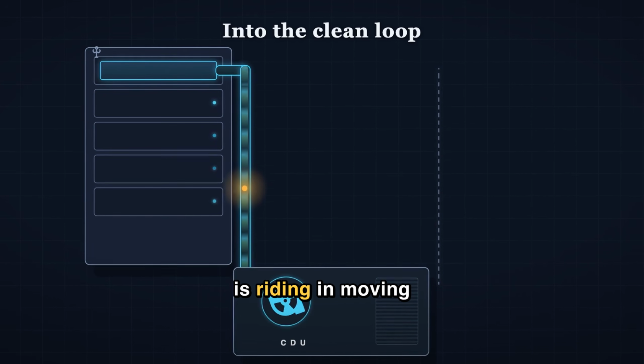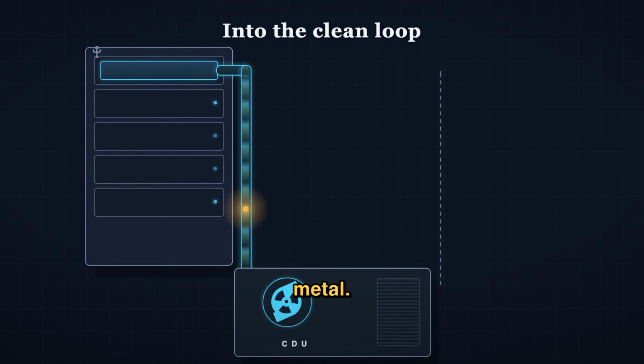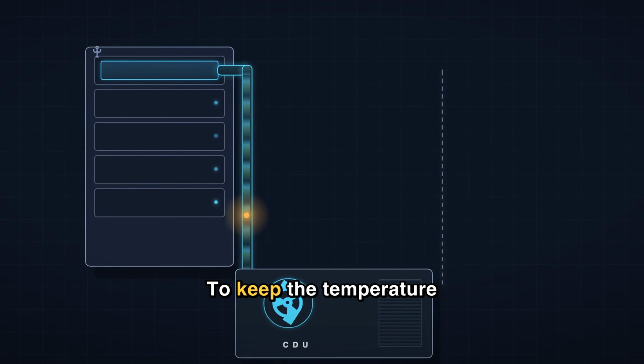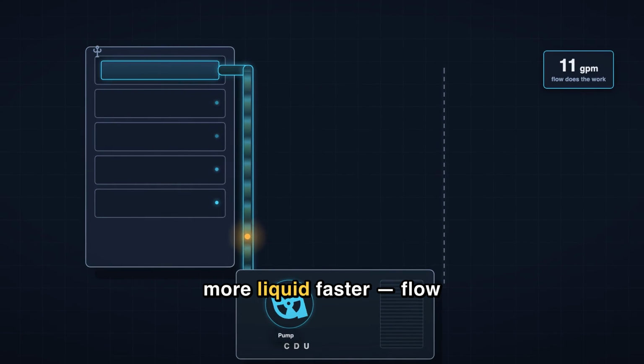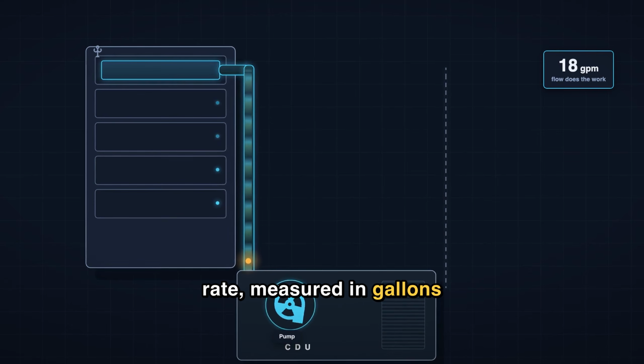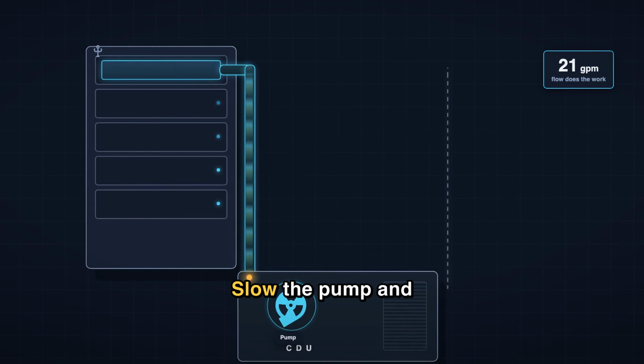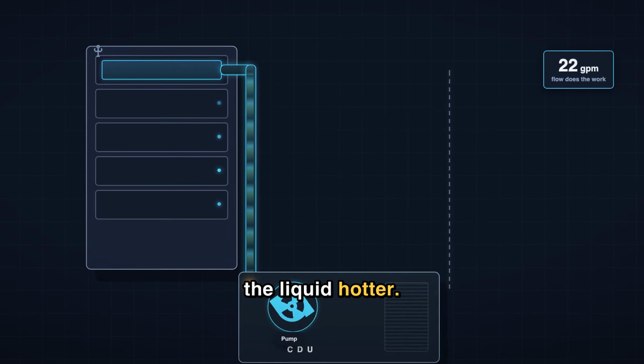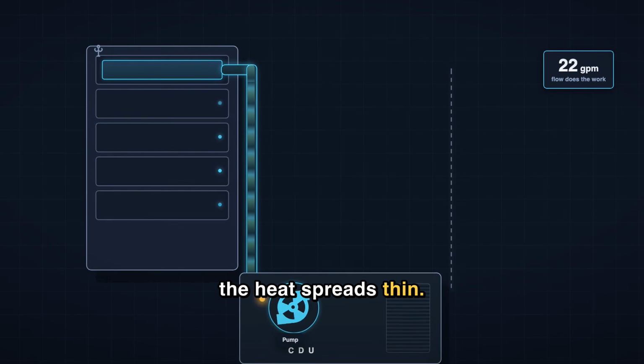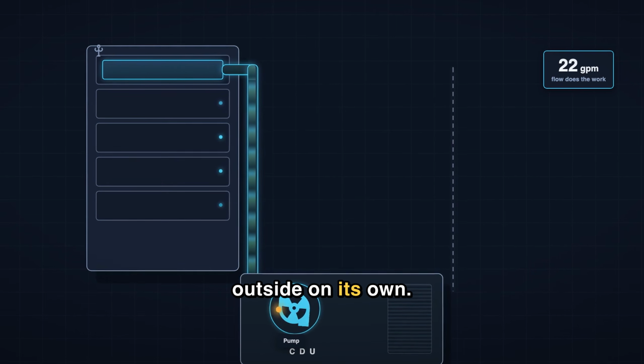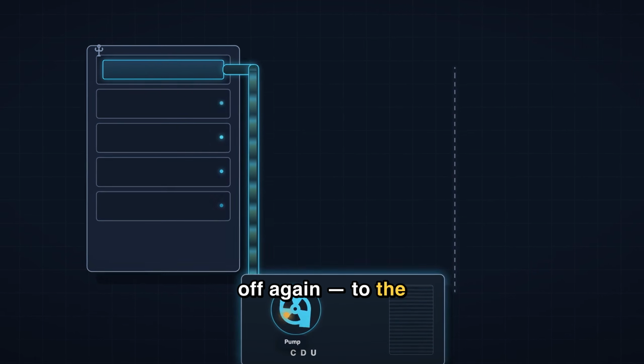And now the watt is riding in moving liquid, not sitting in metal. That changes the rules. To keep the temperature rise small, you push more liquid faster. Flow rate, measured in gallons per minute, does the heavy lifting. Slow the pump and the same watt makes the liquid hotter. Speed it up and the heat spreads thin. But this clean loop can't dump its heat outside on its own. It has to hand off again to the CDU.